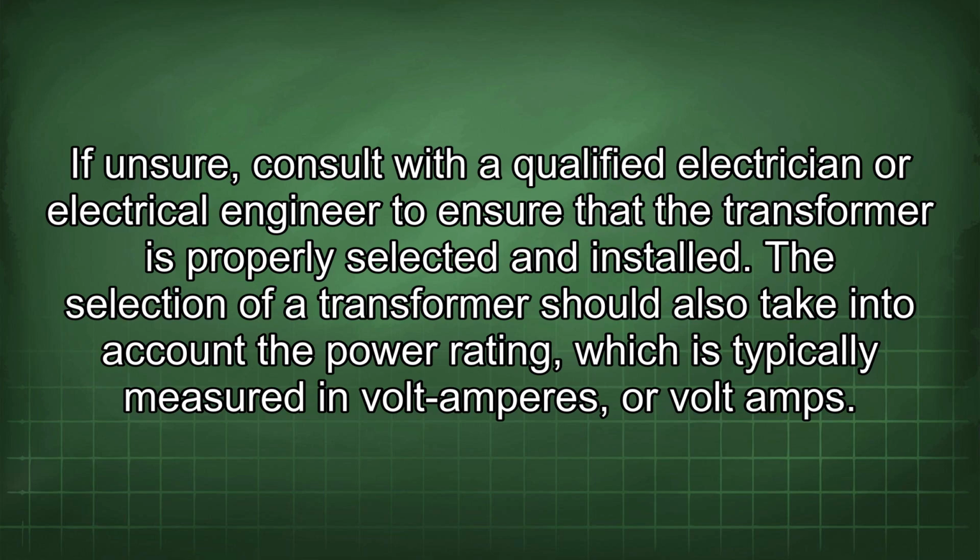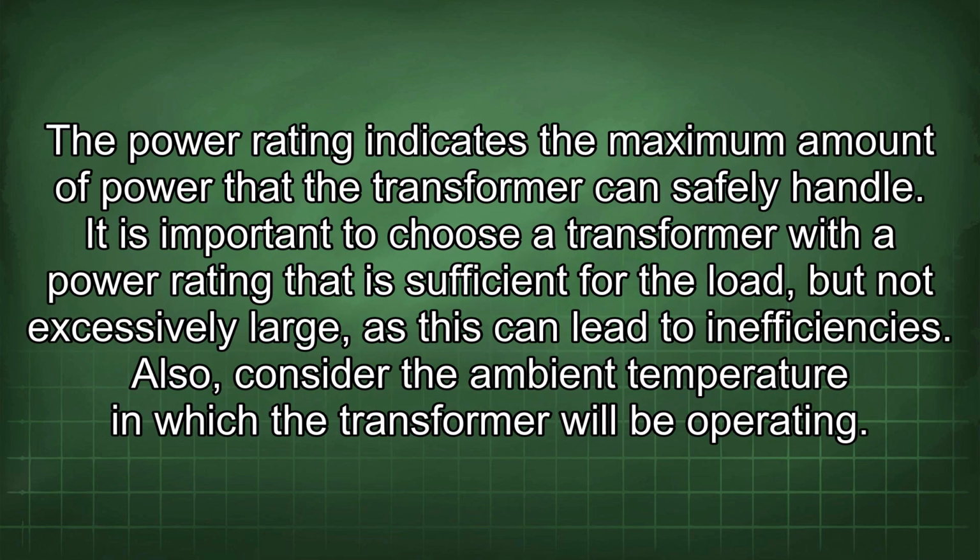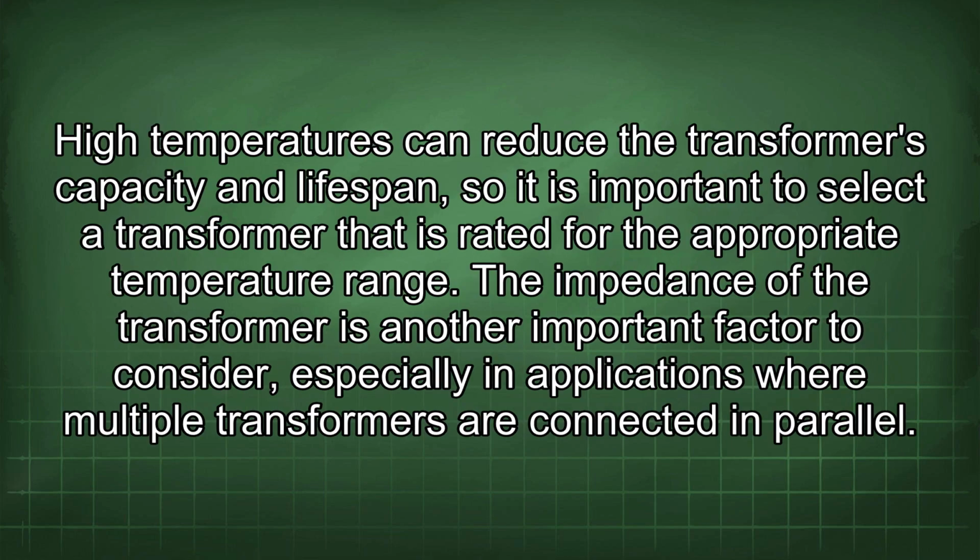The selection of a transformer should also take into account the power rating, which is typically measured in volt amperes or volt amps. The power rating indicates the maximum amount of power that the transformer can safely handle. It is important to choose a transformer with a power rating that is sufficient for the load, but not excessively large, as this can lead to inefficiencies. Also, consider the ambient temperature in which the transformer will be operating. High temperatures can reduce the transformer's capacity and lifespan, so it is important to select a transformer that is rated for the appropriate temperature range.